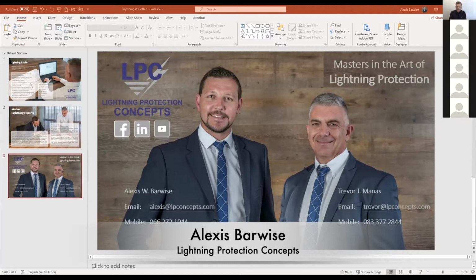So in a rooftop combiner box there's not really anything sensitive electronic to protect — you sit with fuses and a DC isolator. If you're lucky you might have a string monitoring system, then one would definitely protect it. But the requirement for a metal enclosure combiner box wouldn't add value yet, because there's nothing really to shield — you're already shielding the cables via the metallic conduits.